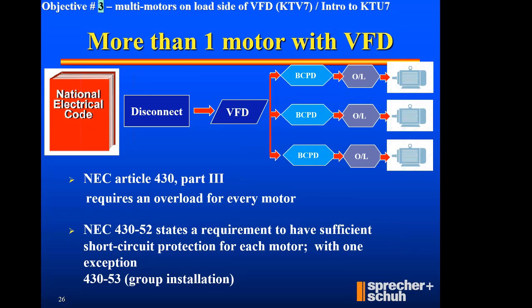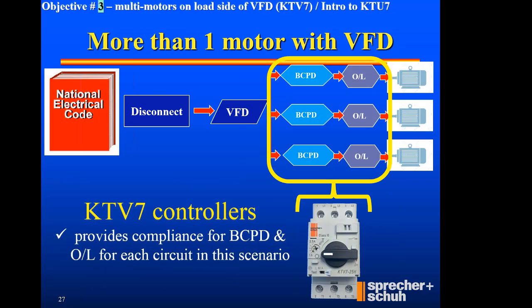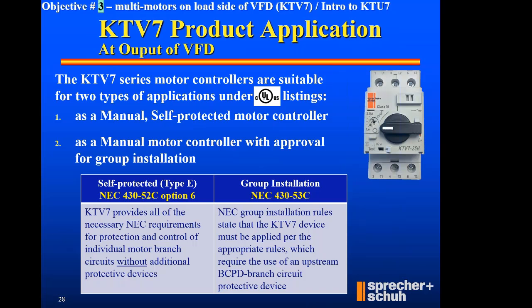However, what we keep reiterating, the National Electric Code says, hey, you've got 3 motors on the load side of 1 controller. Each motor is going to require an overload. So I've got to have an overload for all those motors. Each motor is going to require short circuit protection. And so I've got to have BCPD and overload for each circuit. So that's where the KTV7 component selection can comply with the requirement of branch circuit and overload all in that 1 device. So that's the unique flavor of KTV7.